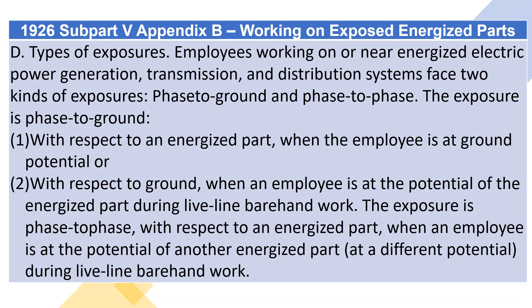Types of exposures: employees working on or near energized electric power generation, transmission, and distribution systems face two kinds of exposures — phase-to-ground and phase-to-phase. The exposure is phase-to-ground with respect to an energized part when the employee is at ground potential, or with respect to ground when an employee is at the potential of the energized part during live-line bare-hand work. The exposure is phase-to-phase with respect to an energized part when an employee is at the potential of another energized part at a different potential during live-line bare-hand work.